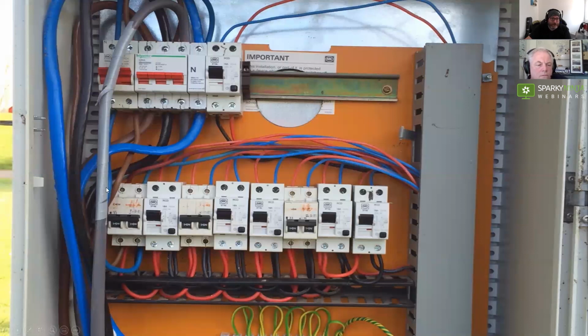And again, there could be sufficient overcurrent protection here for these double poles, but would they need RCD protection? We don't know. If this is a TN-S, maybe. We don't know what the earthing system is here. Anticipate it's probably a TN-S. There's another one that I'm not keen on, which is when you look at those connections, a neutral connection, you've got two cables in that one terminal. I'm not happy with that. Manufacturer may not even like that. No, they're not made to do that, I'm sure of it. And if you start putting more than one cable into a terminal like that, it's not going to do up properly, so you're not going to have a proper connection.